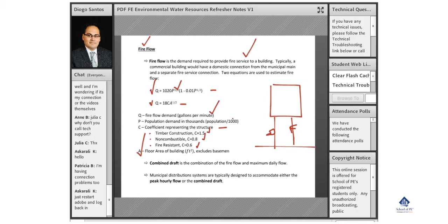A is the floor area of your building excluding the basement. The combined draft is a combination of fire flow and max daily flow, so you can service a fire and also your max daily flow. Municipal distribution systems are typically designed to accommodate either peak hourly flow or combined draft.